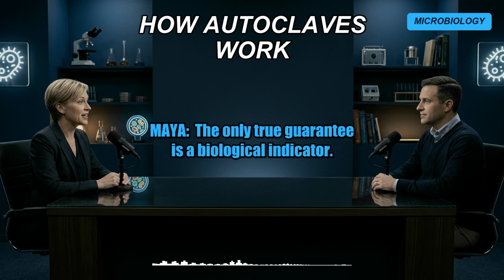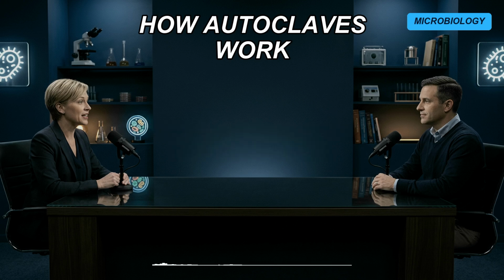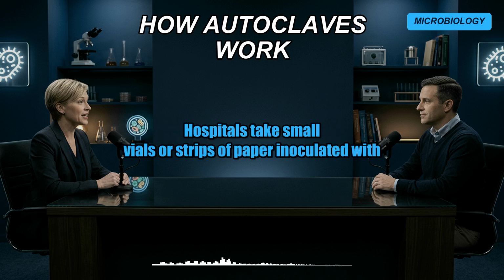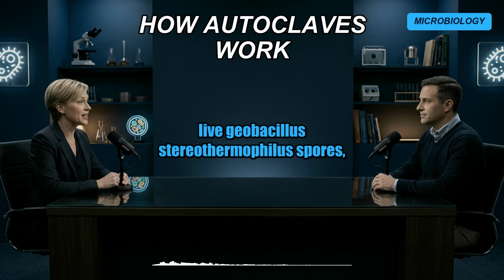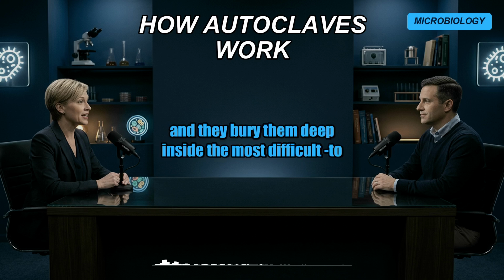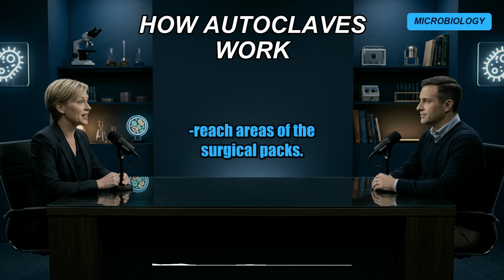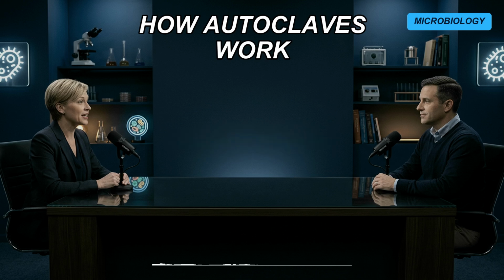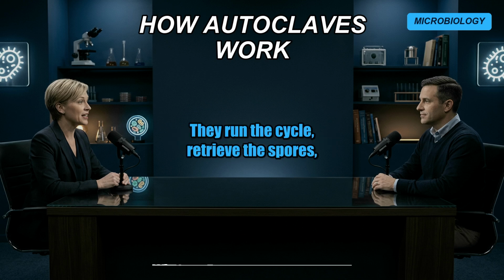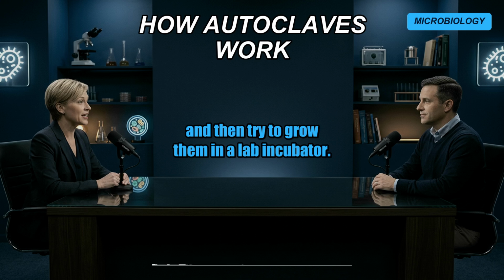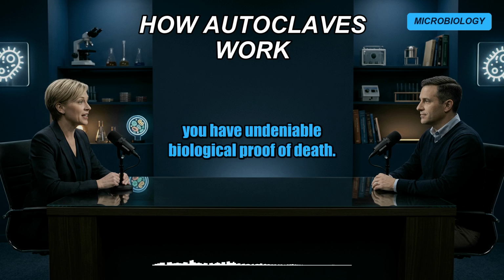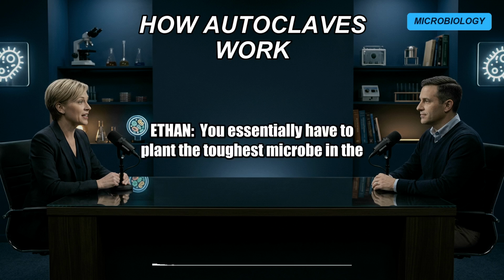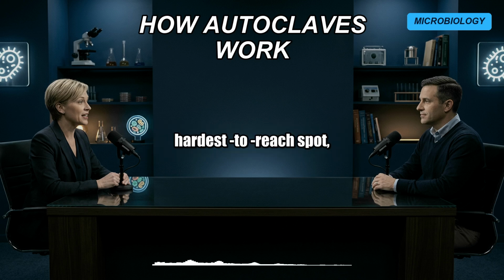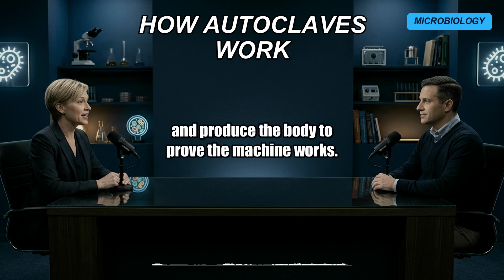The only true guarantee is a biological indicator. Hospitals take small vials or strips of paper inoculated with live Geobacillus stearothermophilus spores, and they bury them deep inside the most difficult-to-reach areas of the surgical packs. Inside the packs. Yeah, they run the cycle, retrieve the spores, and then try to grow them in a lab incubator. If nothing grows, you have undeniable biological proof of death. You essentially have to plant the toughest microbe in the hardest-to-reach spot, assassinate it, and produce the body to prove the machine works.